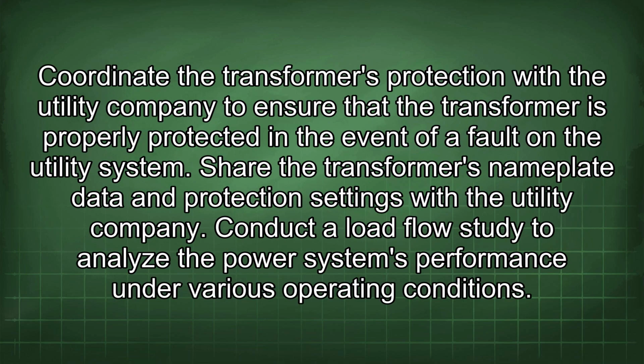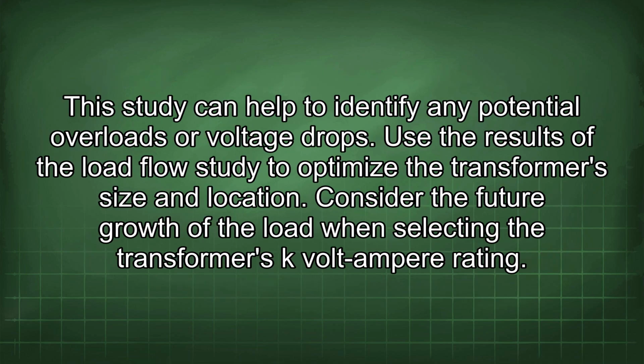Coordinate the transformer's protection with the utility company to ensure that the transformer is properly protected in the event of a fault on the utility system. Share the transformer's nameplate data and protection settings with the utility company. Conduct a load flow study to analyze the power system's performance under various operating conditions. This study can help to identify any potential overloads or voltage drops. Use the results of the load flow study to optimize the transformer's size and location.